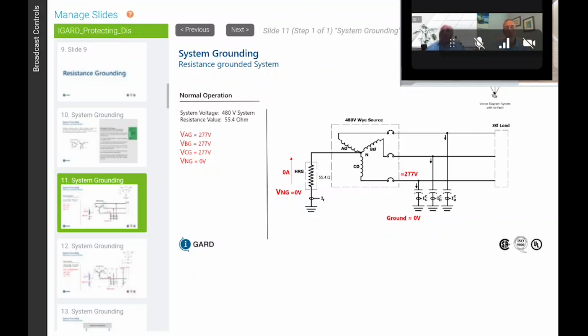to ground. The only way they're going to go back is through the other distributed capacitance, because there's going to be 480 volts. None of the current from your charging current is going to go back through the resistor, even if you have unbalanced loads. So you could have a lot of unbalanced loads here, but the only current that's going to flow back through the resistor is a ground fault current. So this is very important to understand. So you could have 480 volt heaters connected to A and B, B and C, and C and A. If they're unbalanced, they're not going to produce any current flowing through the resistor here.